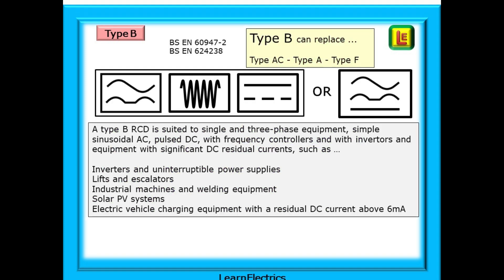Type B RCDs can replace all other RCD types — type AC, type A, and type F. A type B RCD is suited to single phase and three phase equipment, simple sinusoidal AC, pulse DC with frequency controllers, inverters, and equipment with significant DC residual currents — such as uninterruptible power supplies, lifts, escalators, industrial machines, welding equipment, solar PV systems, and electric vehicle charging equipment with a residual DC current above 6 milliamps.